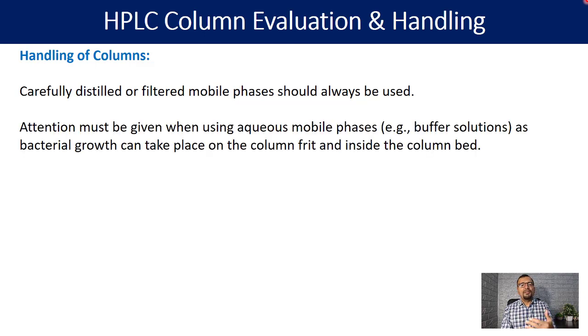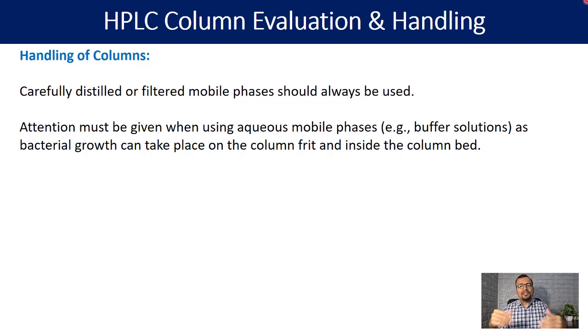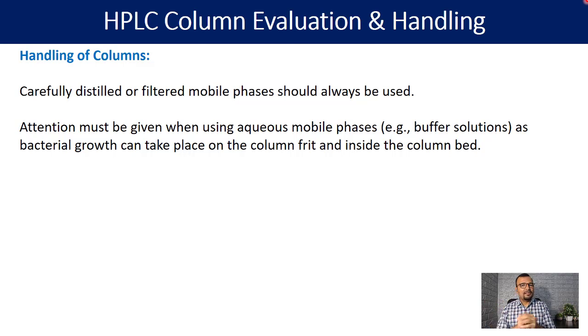Attention must be given when using aqueous mobile phases, for example buffer solutions, because bacterial growth can take place on the column frit and inside the column bed. It is very important to avoid microbial growth caused by high aqueous mobile phase content. Adding organic solvent into the mobile phase where possible is suggested to resist microbial growth.